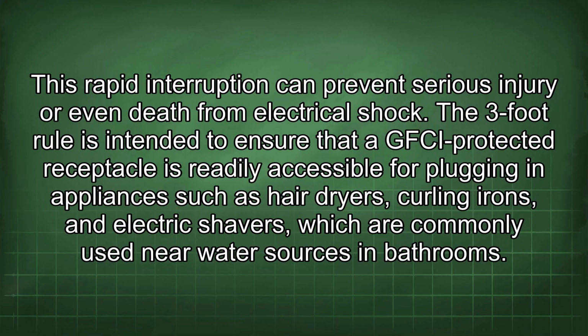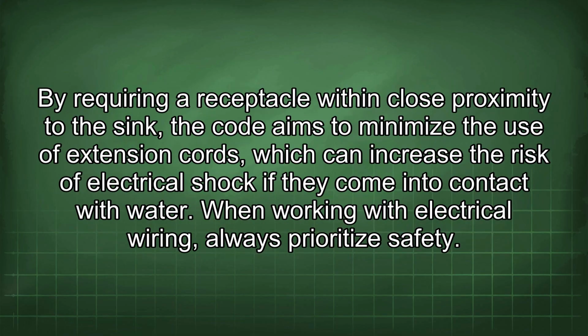The 3-foot rule is intended to ensure that a GFCI protected receptacle is readily accessible for plugging in appliances such as hairdryers, curling irons, and electric shavers, which are commonly used near water sources in bathrooms. By requiring a receptacle within close proximity to the sink, the code aims to minimize the use of extension cords, which can increase the risk of electrical shock if they come into contact with water.